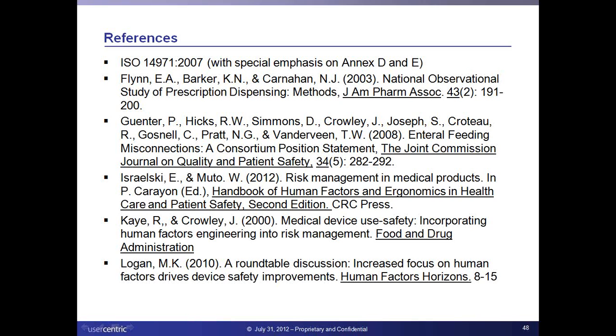Put it into your simulated use training, because oftentimes you'll never really know for sure which way to go. You've got rounds of formative testing, you've got a validation round—implement these contexts of use, see what happens in your formative research, and see whether the controls you've put in eliminate not only confusion but the actions of the use errors.